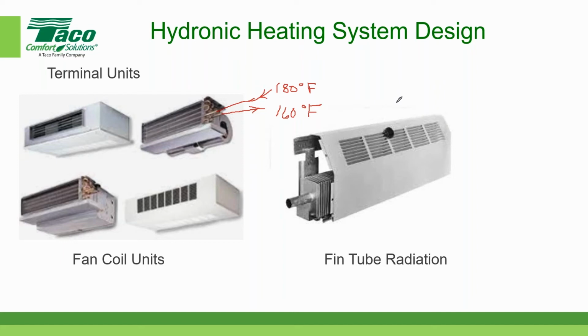The next category of terminal unit is fin tube radiation. It's probably the most popular type of radiation that's out there. As the name implies, the first two words here, fin tube, there is the tube right there. And generally speaking, the tubes are usually copper, and the fins themselves are mechanical or press fit onto the tube, and the fins are usually aluminum. And then it's covered by a metal cover. This particular one has a damper that's inside. You can't actually see the damper, but it's controlled by a manual knob here. So as I turn that knob, the damper opens and closes.